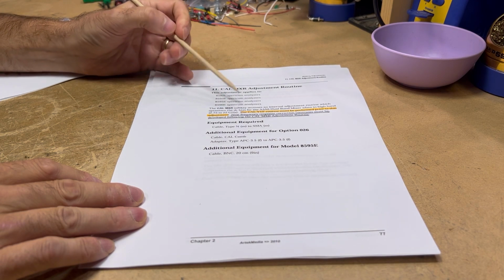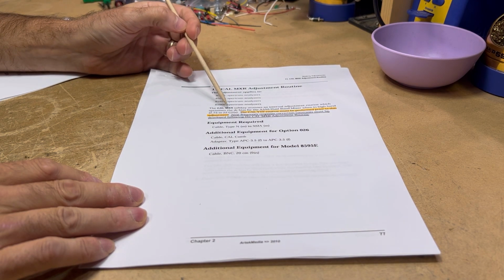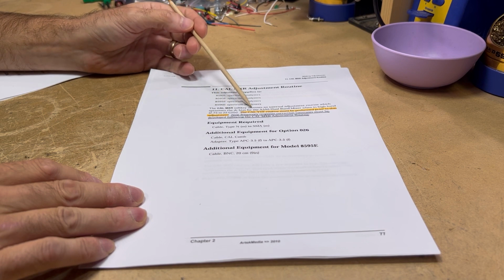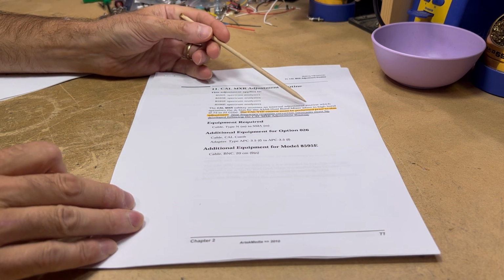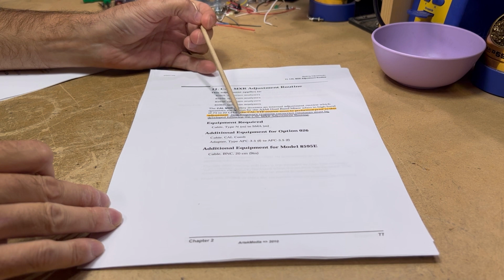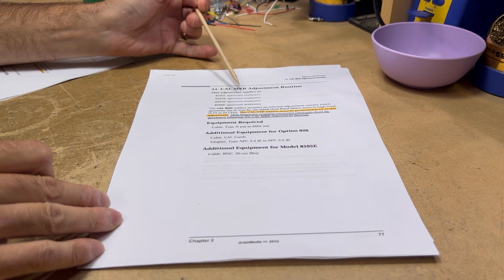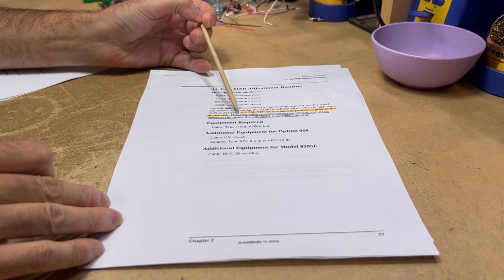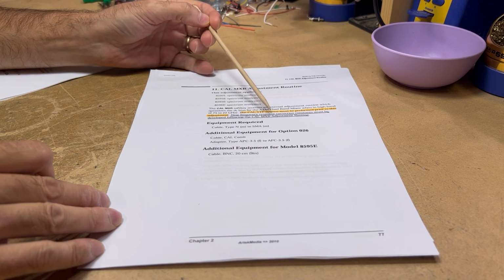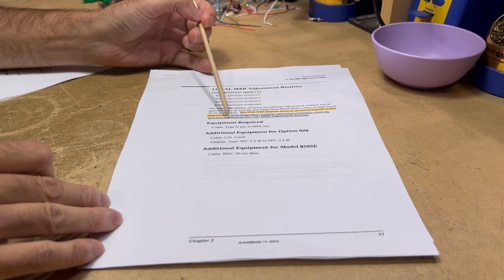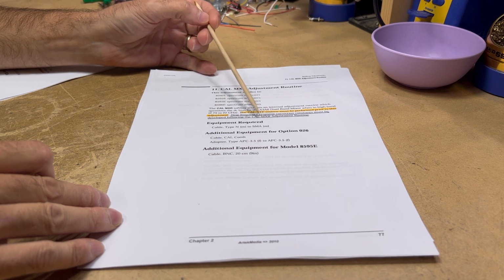which, if you look at this section here, the cal mixer, optimizes the DC bias of the dual band mixer when in the high bands. And one thing to note here too is that when you run this routine, you will need to make new frequency response correction constants. So they must be developed following the cal mixer adjustment routine.